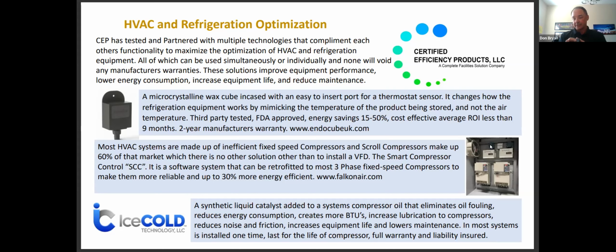And rather than measuring the air temperature of the cooler, so that every time somebody opens the cooler door the thermostat says it's going up and the compressor kicks on, it actually measures the temperature of the product being stored inside of the walk-in cooler or freezer. So you get compressors that are now running according to the product being stored, rather than the air temperature. It's been tested all over the world. We're installing thousands of these in convenience stores right now, and you can get anywhere from 15 to 50% savings on the compressor run times that you were getting previously without using one of these. So it's a very cost-effective solution, very easy and non-disruptive to implement, and we're getting great results on that.